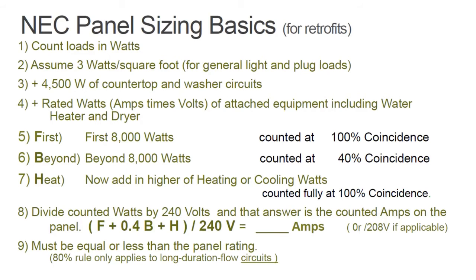Beyond the first 8,000 watts of things you've counted around the house, they assume that stuff will only be on, there's only a 40% likelihood that it's on. So we don't make you upsize your panel just because you happen to own this stuff. It doesn't all run at once. So they use a 40% coincidence factor for that. And then the one exception is the larger of either the heating or cooling load. So if you're using the heat pump, we just count that fully as being 100% coincident.